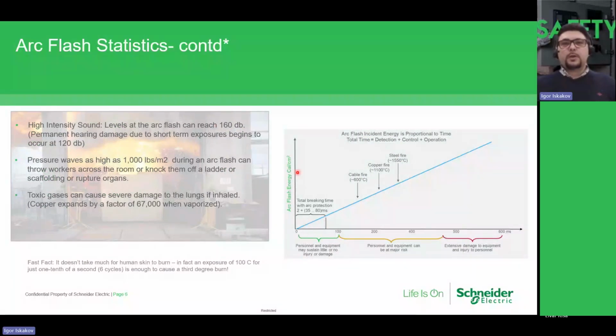Here is the curve of the arc flash, which is taken in kilocalories per square centimeter against time. From 0 to 100 milliseconds, there is small damage to the equipment, maybe some scratches on the insulators, and people can be injured, but they survive after recovering. And this is also confirmed by statistics. But when we go to longer times, from 0 to 200, 400, even 500 milliseconds, the extremity of the arc flash increases.